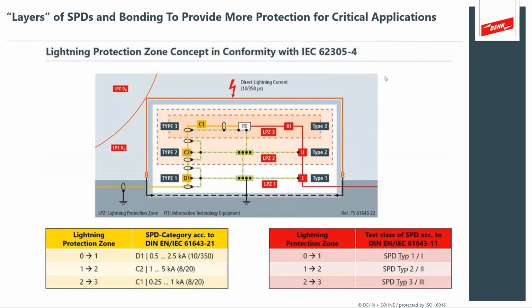That's the perfect application for surge protection devices, because you're not separating and you're not bonding, but then you can control the voltage so it doesn't flash through the insulation.